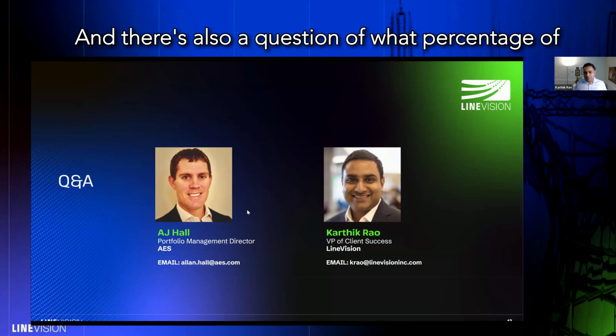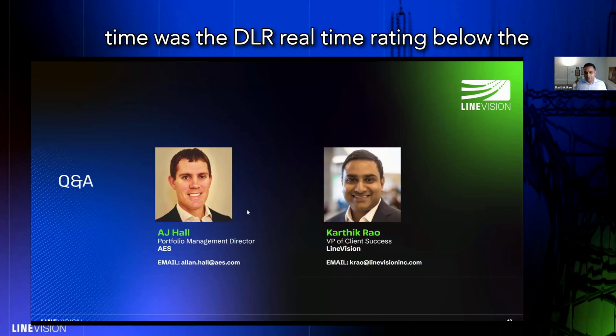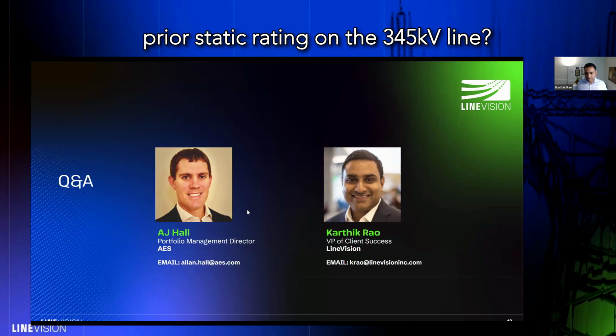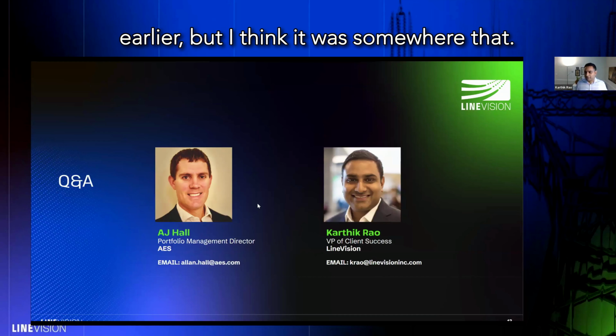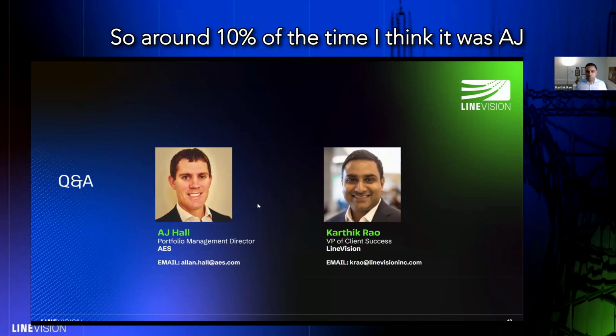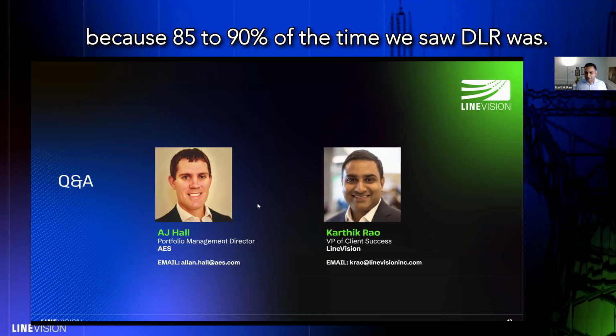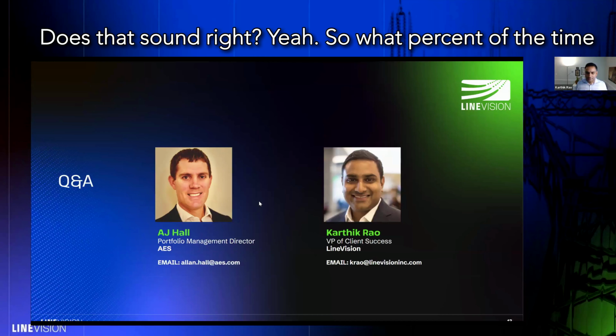There's also a question of what percentage of time the DLR real-time rating was below the prior static rating on the 345 kV line. I think we had that in an earlier slide, somewhere around 10% of the time, because 85 to 90% of the time we saw DLR was greater than static. Does that sound right? Yeah.